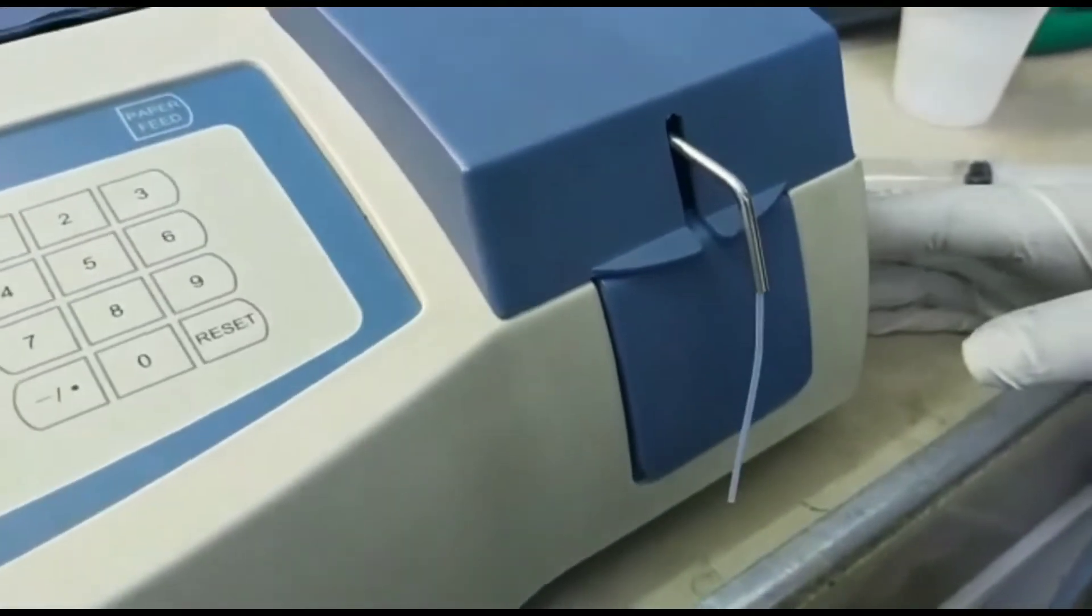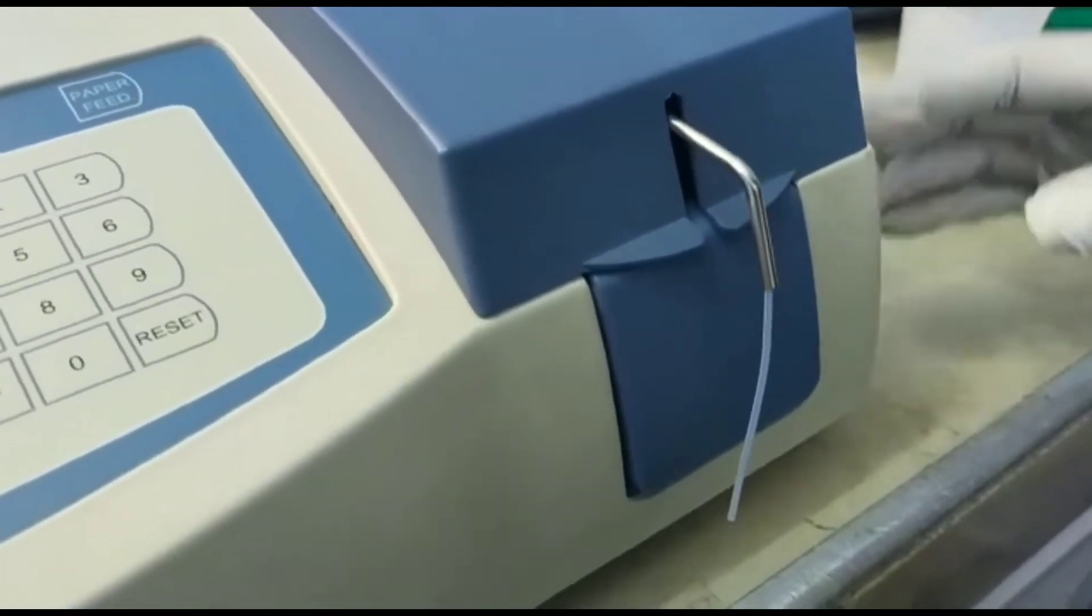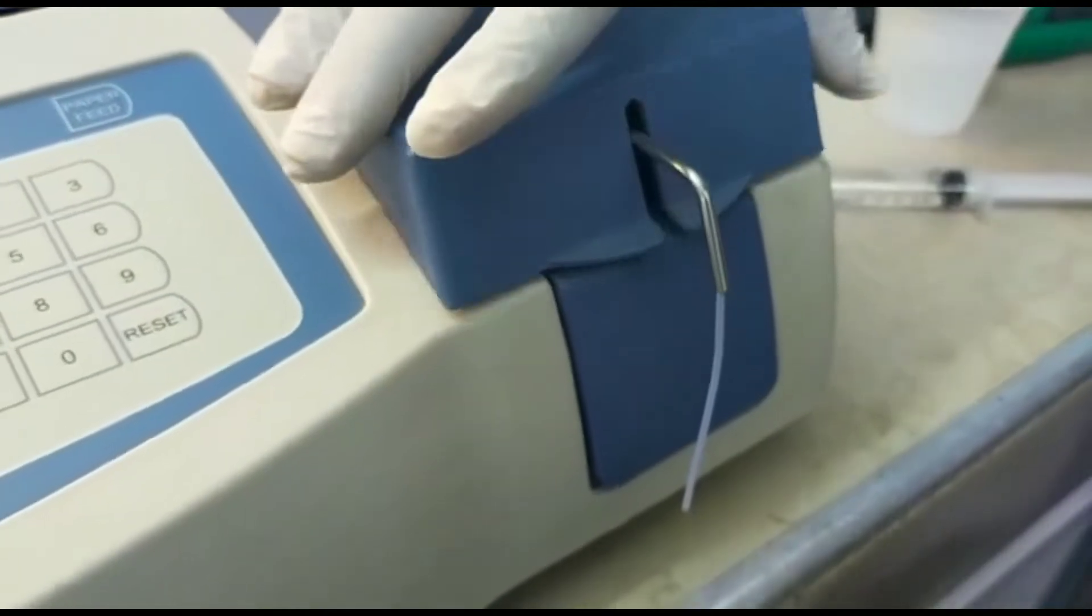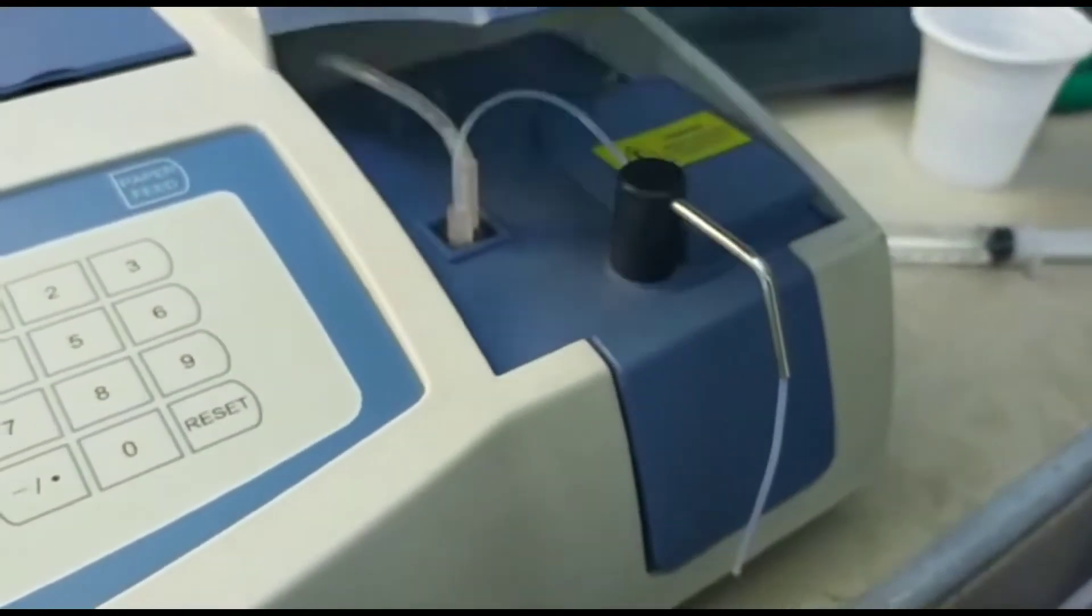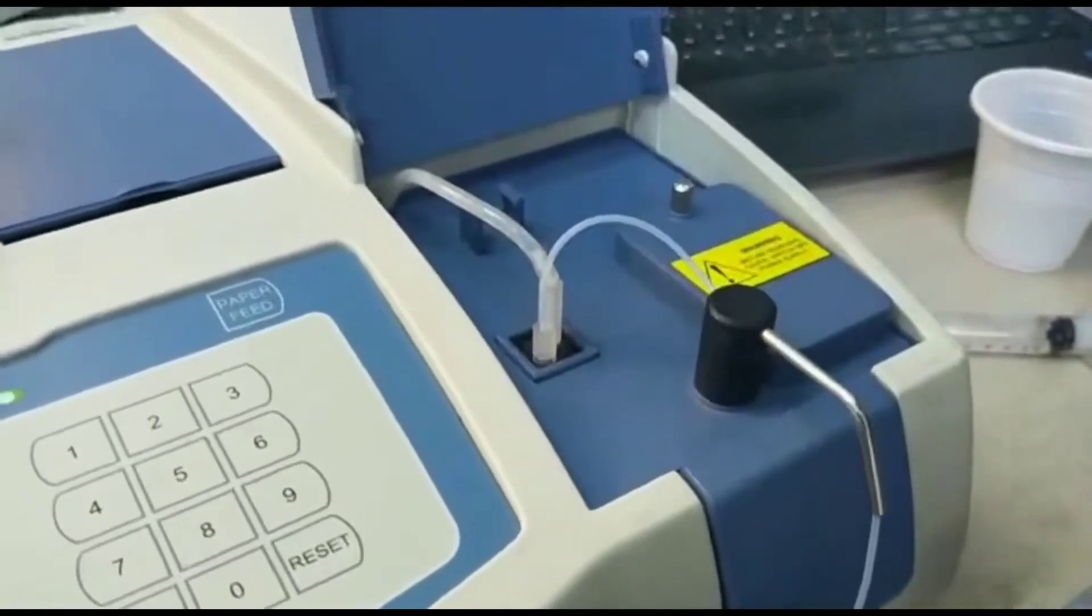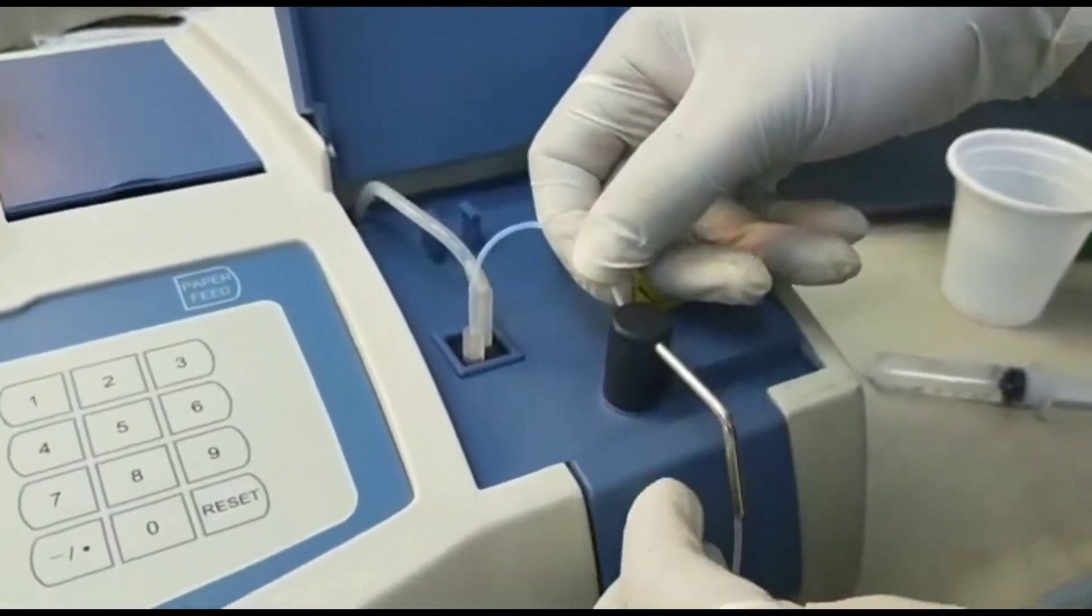Sometimes the flow cell gets blocked so you need to clean the flow cell. To clean it you need to open the cover which is on the right hand side.